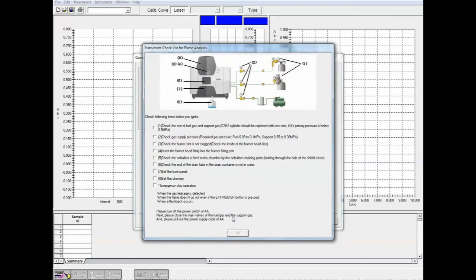We'll hit OK. Now it has a series of instrument checks that we can do. So we're checking the fuel and the support gas, checking that our cylinders don't have any leaks, so we've already done that. We're checking the gas supply pressure, we've already done that as well. We're checking that the burner slot is not clogged, so we want to physically look at the burner, make sure there's nothing in there that could be obstructing the flame. Make sure that the burner head is firmly sitting in its port. We're checking that the nebulizer is attached to the chamber, so we're doing physical checks on all of these things.